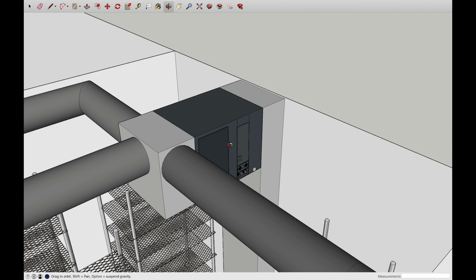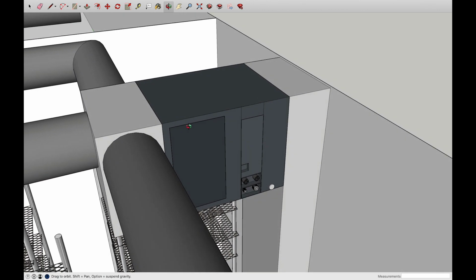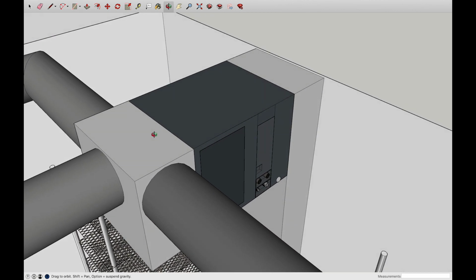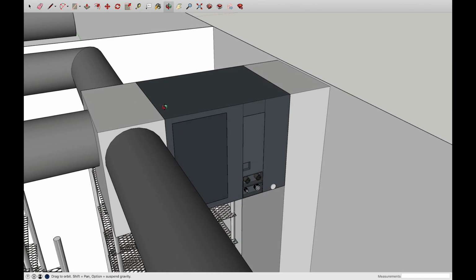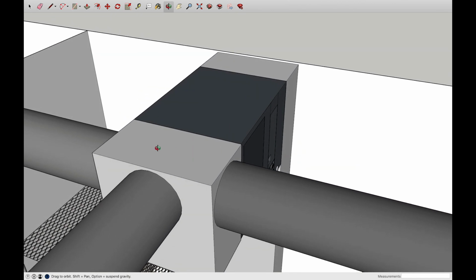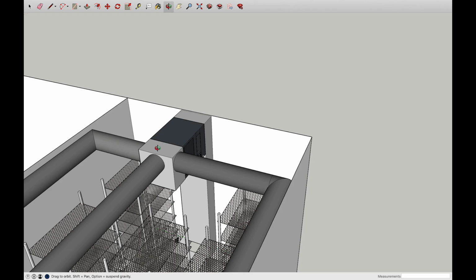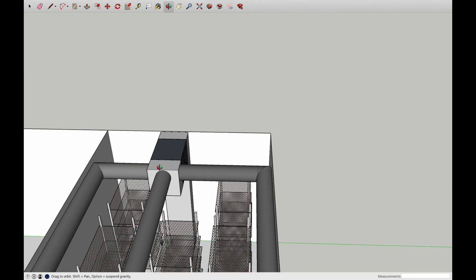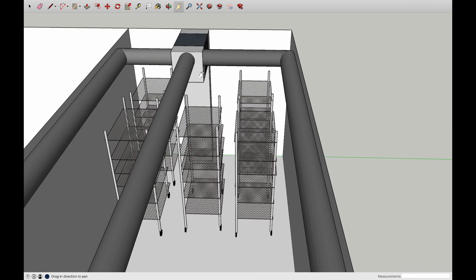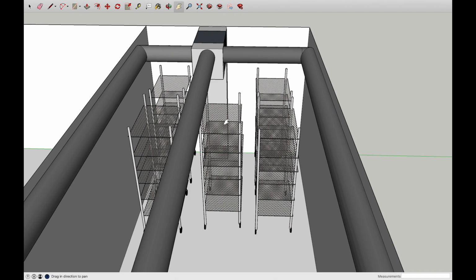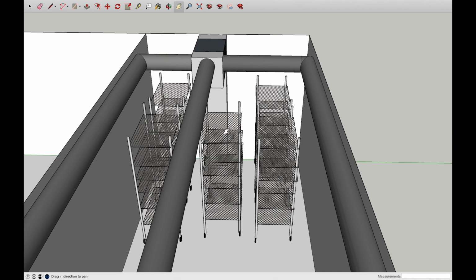The real unique part about this, other than it being a mass dehumidifier, is our airflow. Where traditionally you might get 1,000 CFM or so out of a 2-ton air handler, we're running over 2,600 CFM. Why this is so important is that you're going to have a lot more air turns per day. This particular room is going to be turning over roughly every 45 to 60 seconds, which gives us tremendous airflow, and that's very important when curing and drying product.